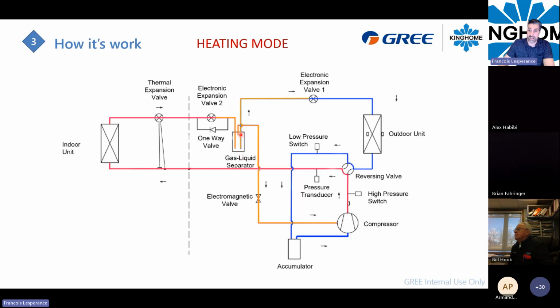So we are here in that tank. We will pump 100% liquid refrigerant out of it, and we will hit the first EEV right here, and this one will act as your metering device at that point. So your high pressure right here is going to be low pressure on the other side. And then you will hit the outdoor coil, go back through the reversing valve, and then go back to the accumulator and the compressor again. So this is how it works in heating.